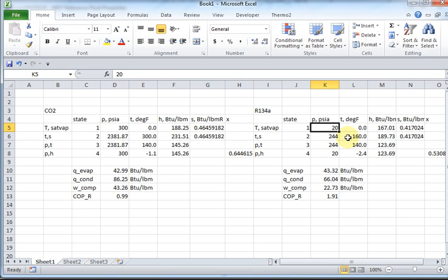But look at this. I got 300 psi. If I have a leak there, it's really going to gush out, right? And now this is a lot higher pressure right in here. I mean, that's ridiculously high pressure. All right. So this is reasonable pressures. It's going to be a lot easier to seal it, maintain the seals with rotating machinery or penetrations through the seals. And you have a lot better coefficient of performance.